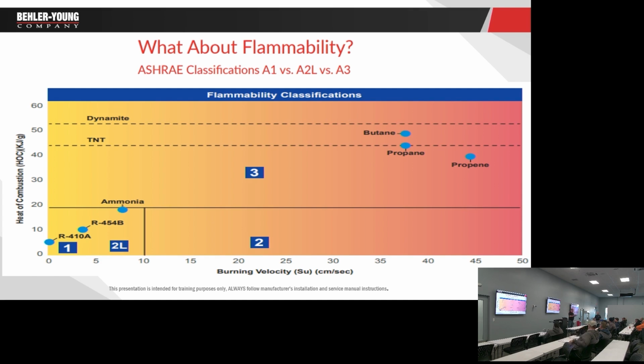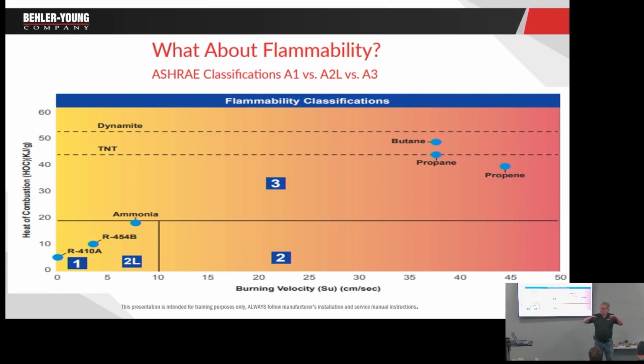So remember the LFL, because you're going to see that written all over the place. Lower flammability limit. It has about a 12% flammability limit, meaning I need to fill this room with at least 12% 454B before it'll ignite, if it would ignite. Once I get to that level, a spark won't ignite it, a flame will ignite it. It has a very low flame spread, and if you take the flame away, it goes out. It can't sustain ignition on its own. So you get some idea what slightly flammable means. It is not propane. It does not contain propane. If you look at propane, it's way over here. That has a very high flame spread and a very low ignition point.